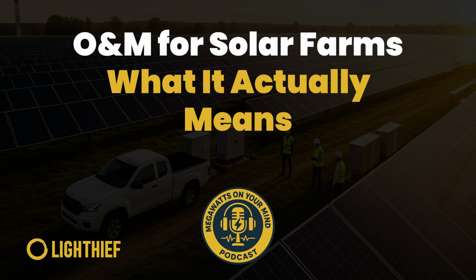Every modern solar farm has a monitoring system. At minimum, this includes the inverters reporting their production. Better systems have string-level monitoring. Each string of panels reports separately, so you can identify problems at a much more granular level. Weather stations provide irradiation, temperature, and wind data. Some systems include soiling sensors to measure how dirty the panels are. All this data goes to a SCADA system, supervisory control and data acquisition, essentially a software platform that collects, stores, and displays the performance data.